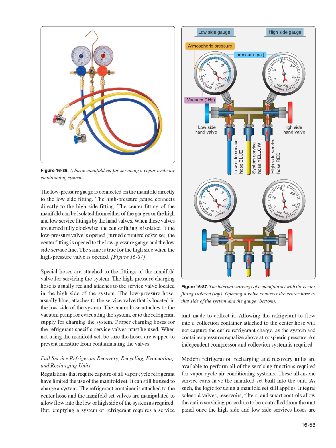Full service refrigerant recovery, recycling, evacuation, and recharging units, and regulations that require capture of all vapor cycle refrigerant, have limited the use of the manifold set. It can still be used to charge a system. The refrigerant container is attached to the center hose and the manifold set valves are manipulated to allow flow into the low or high side of the system as required.